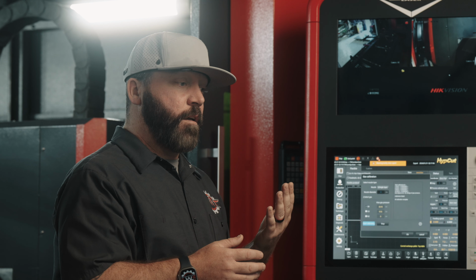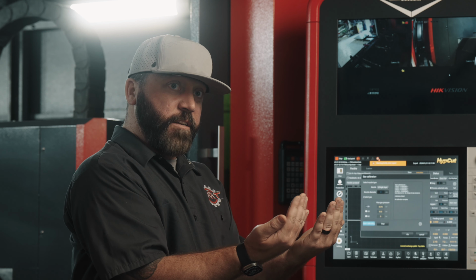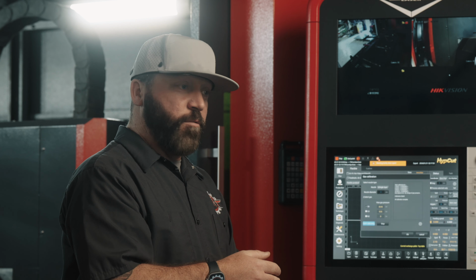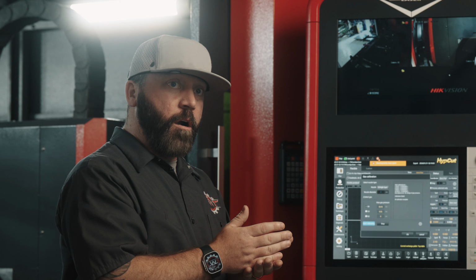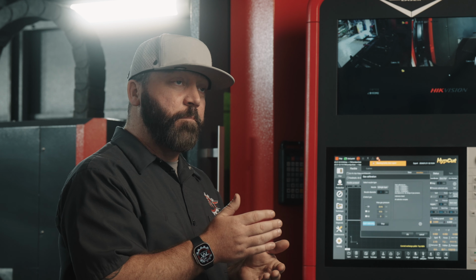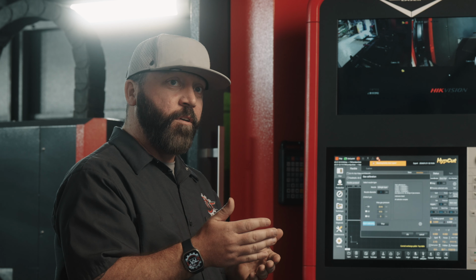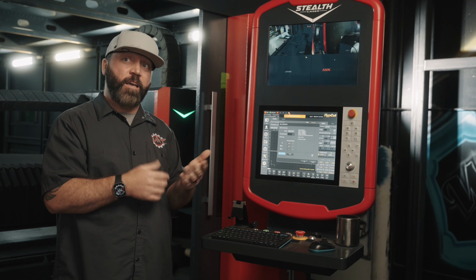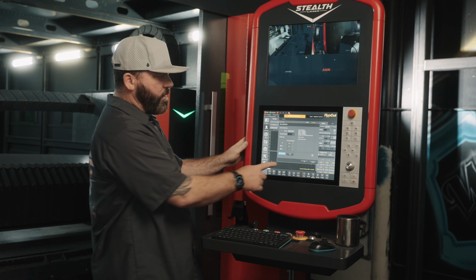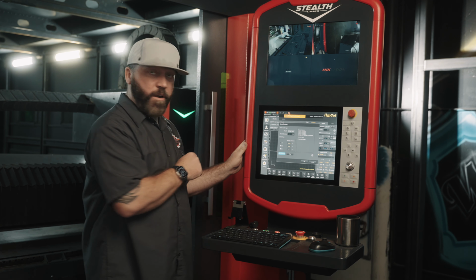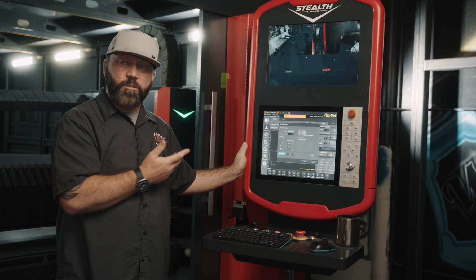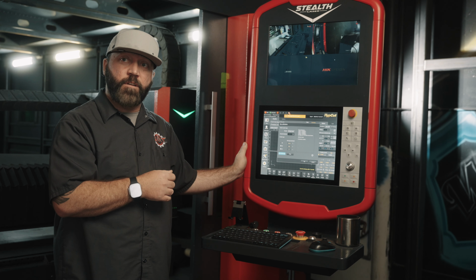It's like having two tire gauges next to each other, and checking the pressure, and one says 50 and one says 55. In cutting, we're measuring it in bar or MPa, so it's a very detailed, minute measurement. If you're 0.8 bar on oxygen, but you need 0.9 or 1.0, that's a big difference. That's the difference between a good cut and a bad cut. And we have the ability to do air, oxygen, or nitrogen on this machine in terms of calibration to make sure that the absolute pressure at the nozzle is perfect.